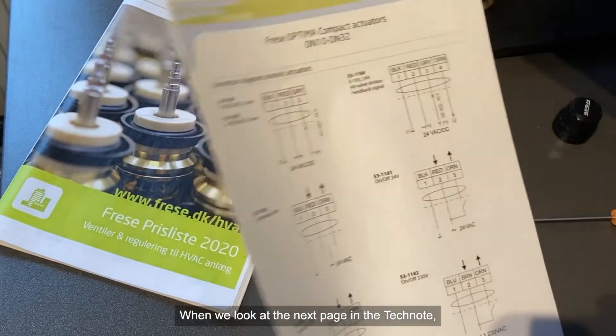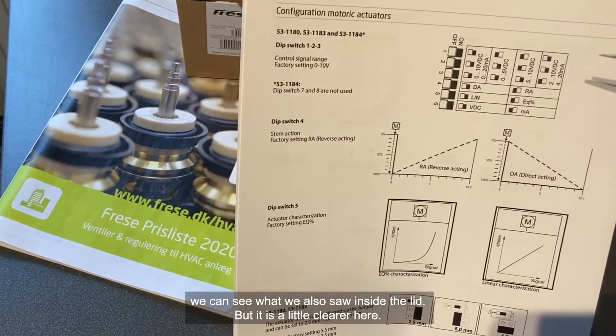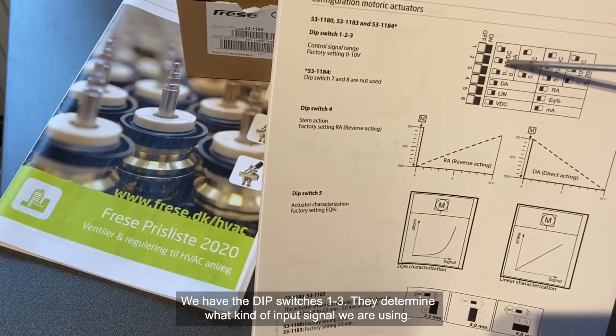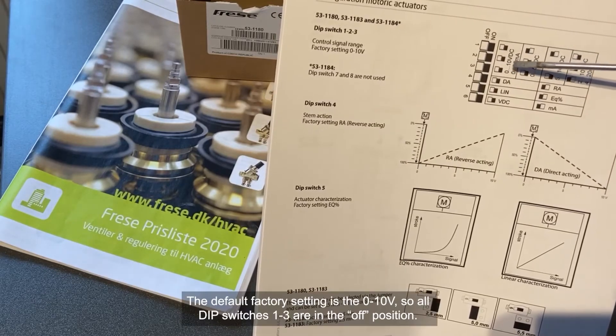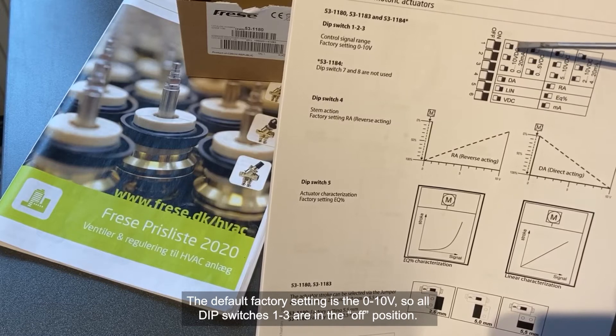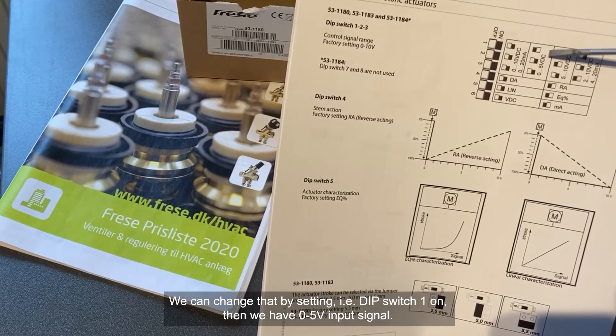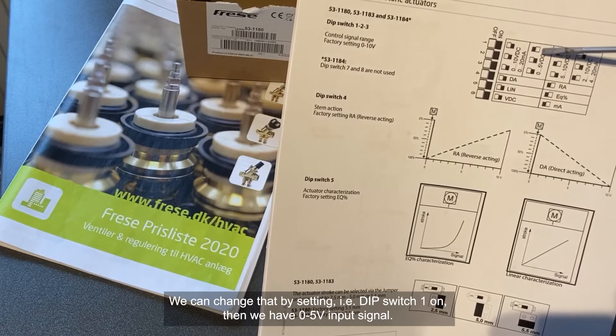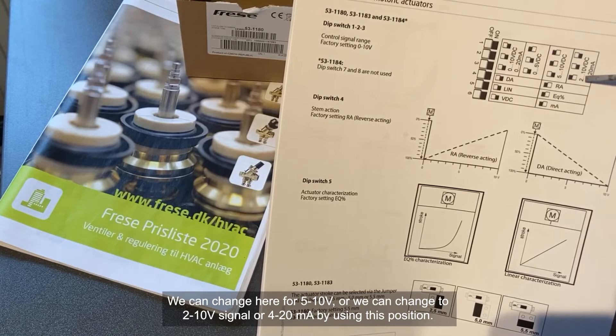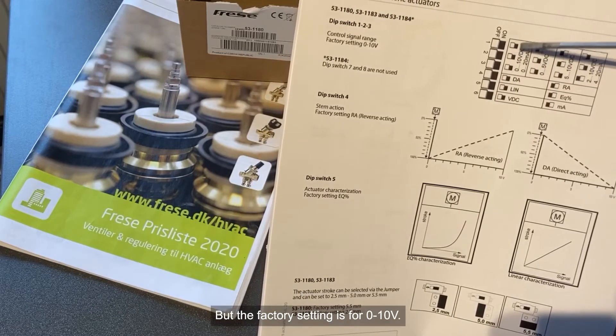Looking at the next page of the Technote, we can see what we also saw inside the lid, but here it's a little more clear. We have dip switches 1-3, which decide what kind of input signal we are using. The default factory setting is 0-10 volt, so all dip switches 1-3 are in the off position. We can change by setting dip switch 1 to on for a 0-5 volt input signal, or configure for 5-10 volt, 2-10 volt, or 4-20 milliamp. But the factory setting is for 0-10 volt.